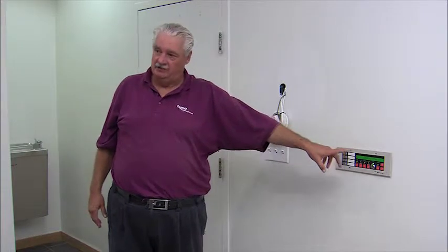After that smoke detector stays dirty for a certain amount of time, it could turn to excessively dirty. You don't want to let it get that far, because once you get to excessively dirty, it could mean false alarm, fire trucks, and all that. So if you see a dirty trouble, that needs to be called in for service. Say, hey, we got a trouble here, a dirty detector, it has to be replaced. We've already replaced that one already. Probably because we needed to have it installed for inspections before construction was done. Yeah, so much haze in here. Yep. So that one, that should be it.